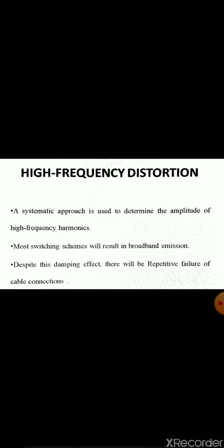So next is emission by individual generators. We have a number of filtering techniques which will be compared with a 110 kilowatt converter connected to a wind turbine. The current waveform for this full power converter connected to a 33 kV feeder has a total harmonic distortion of 6.5%. So there will be a significant ripple visible in the waveform.